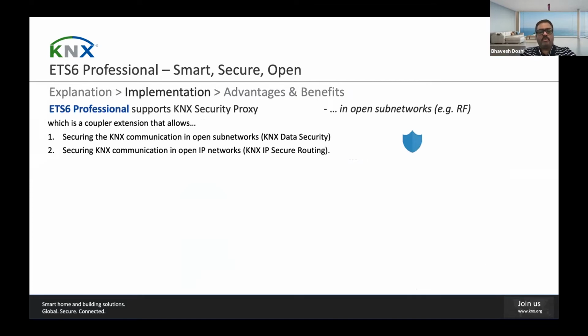KNX secure protocols will secure several use cases where KNX communication shall be limited to a group of authenticated devices, or the entire communication shall be protected against eavesdropping or manipulation. However, what happens if you want to extend an existing KNX installation consisting of only plain devices with new KNX secure capable devices that shall operate securely? Here is where the security proxy comes into play.